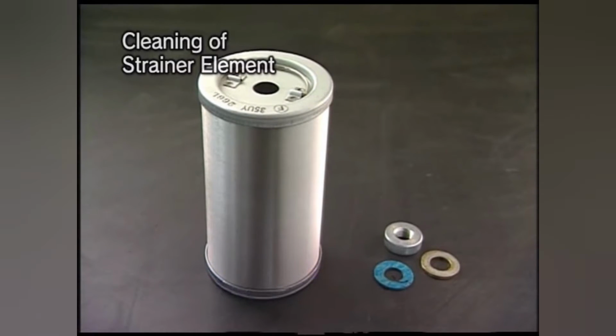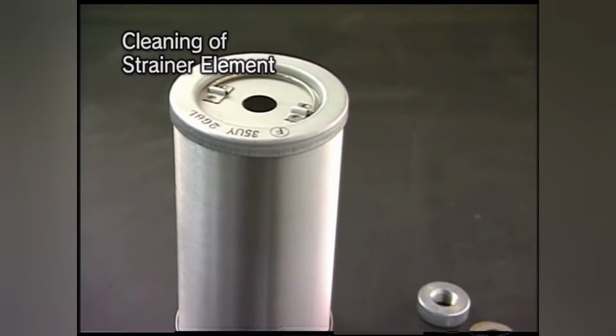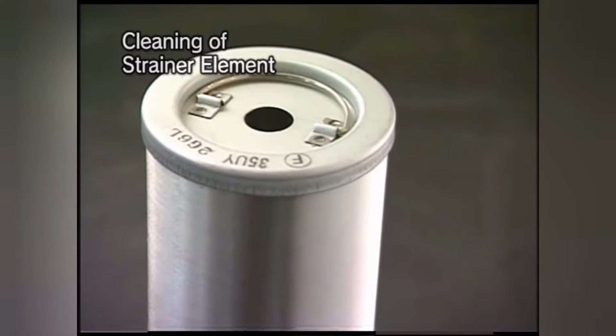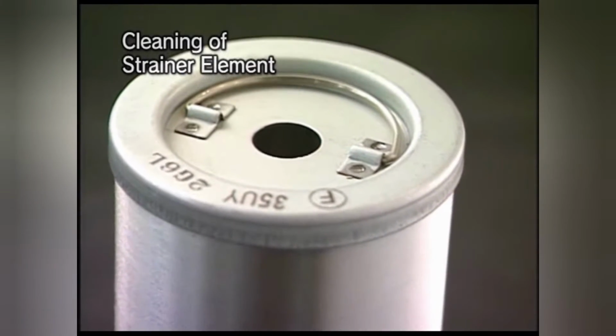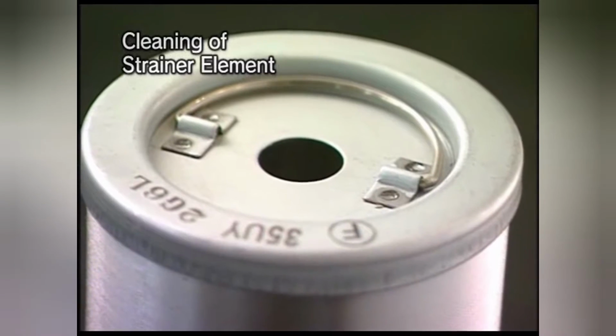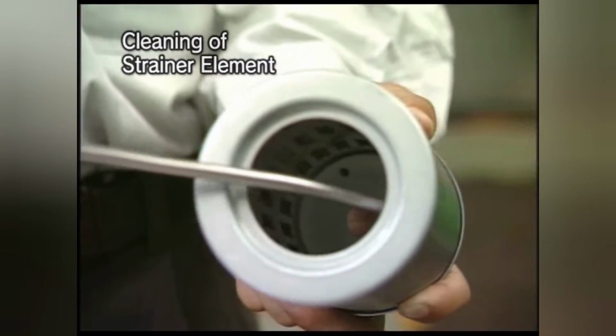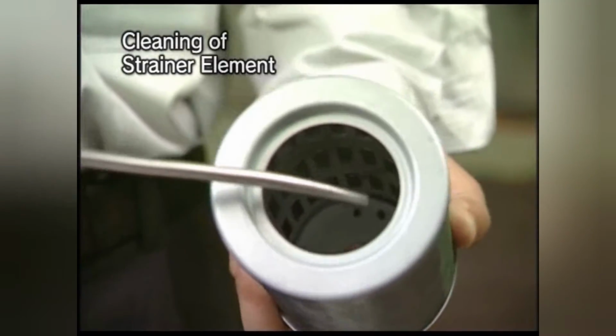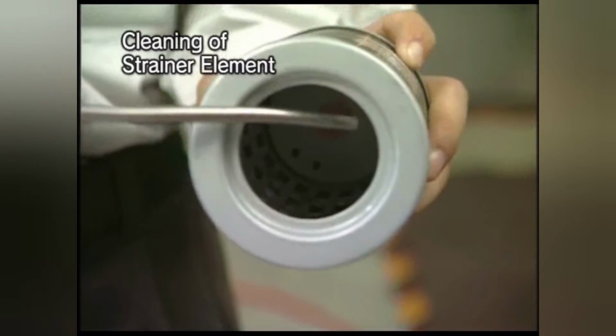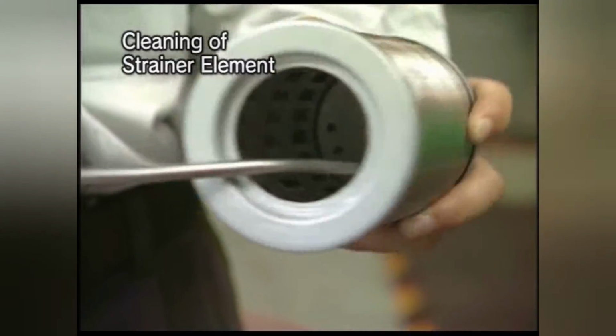Remove the sludge on the surface with a nylon brush by soaking the pulled out element in light oil or washing liquid. Blow the compressed air of between 0.3 and 0.5 megapascals from the inside of the element.